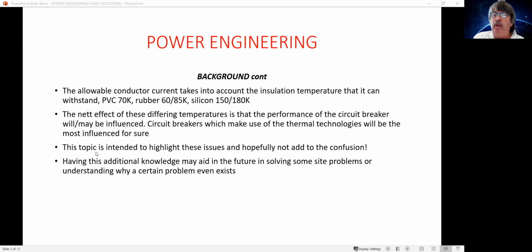And other alternatives to PVC, now PVC is considered to be a 70 degrees Kelvin type temperature rise, so it's allowed to get to that without damage. You do get some rubbers out there, of course, the nitrile type rubbers and the typical rubbers. They could be anything from a 60 to 85 degree Kelvin. And we're all aware today the massive advancement of silicone in many things, including cable. And that cable could withstand 150 to 180 degrees Kelvin, which is a huge thing. Obviously, the net effect on that type of temperature, if you're using that type of cable, you're going to have a problem with the circuit breaker. There's no doubt that over time, you will definitely have something go wrong somewhere down the line where you have a nuisance tripping or a failure to do something using that type of cable.